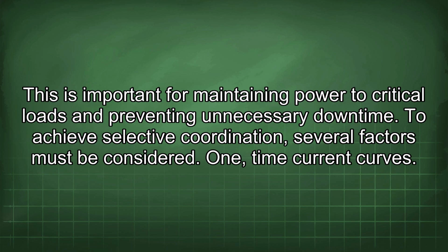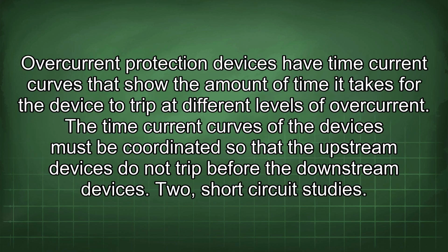To achieve selective coordination, several factors must be considered. 1. Time current curves. Overcurrent protection devices have time current curves that show the amount of time it takes for the device to trip at different levels of overcurrent.